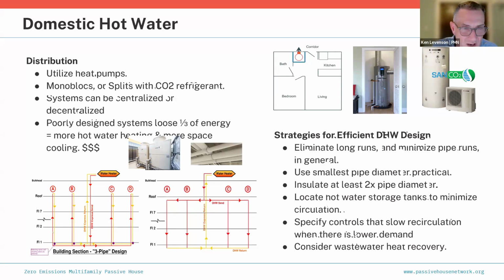Now, we're going to insulate the pipes well, but it's still heating the building. So the more pipe you have, the more heat you're losing, and you have to make it up with cooling for the space, because you're heating the space unintentionally. So we want to find strategies to minimize the pipe lengths.